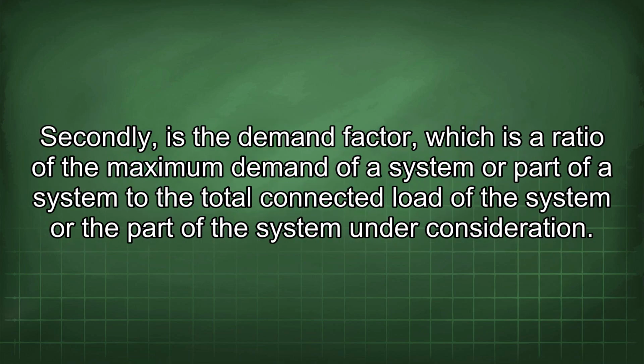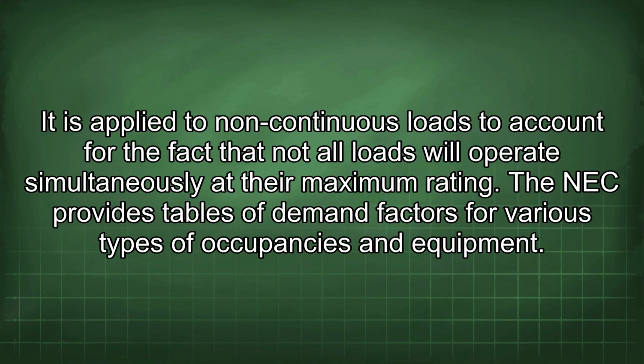Secondly is the demand factor, which is a ratio of the maximum demand of a system or part of a system to the total connected load of the system or the part of the system under consideration. It is applied to non-continuous loads to account for the fact that not all loads will operate simultaneously at their maximum rating. The NEC provides tables of demand factors for various types of occupancies and equipment.